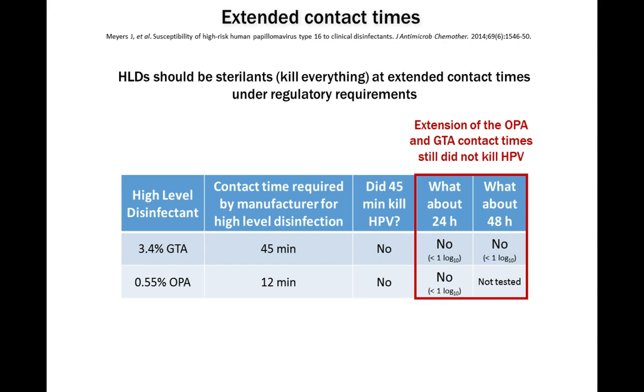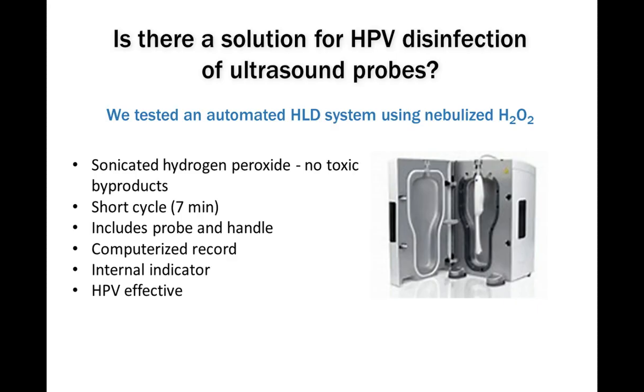So we decided to use extended contact times. High-level disinfectants should be sterilants, meaning killing everything at extended contact times under regulatory requirements. So using our GTA, we used contact times of 24 and 48 hours, and for the OPA, we used a contact time of 24 hours. And even at these extended contact times, neither OPA or GTA were able to kill or deactivate HPV at any measurable amount.